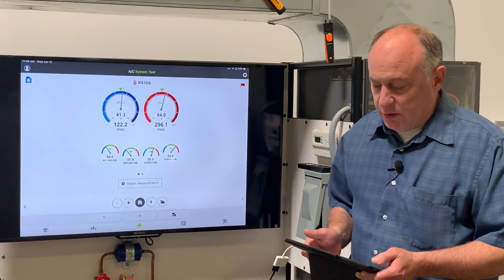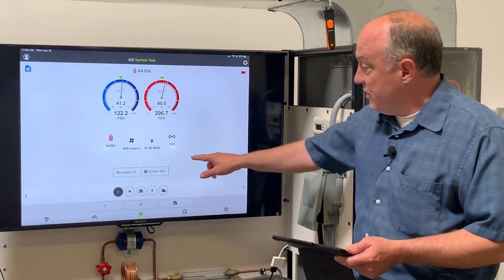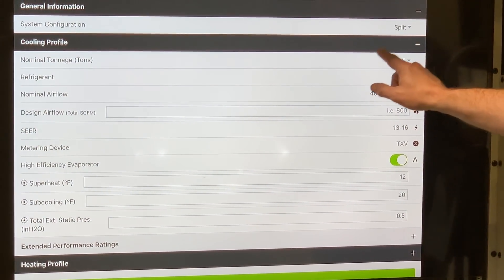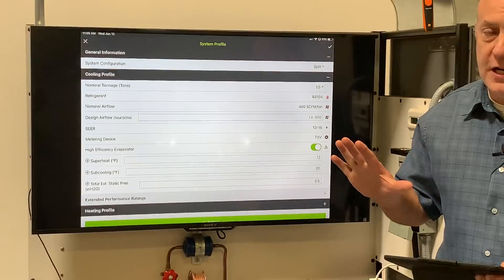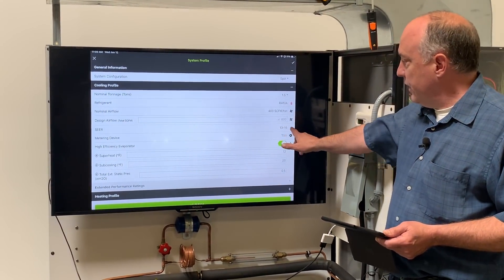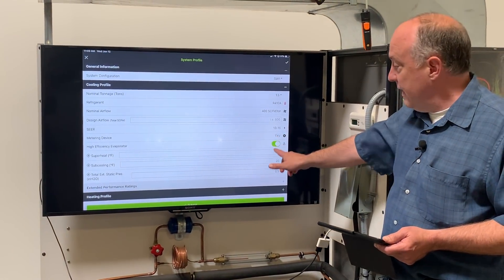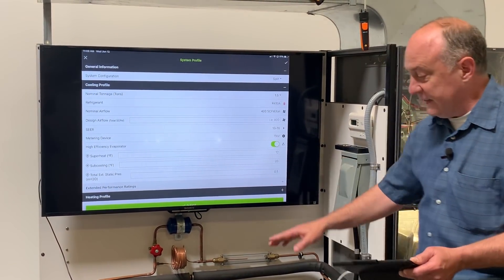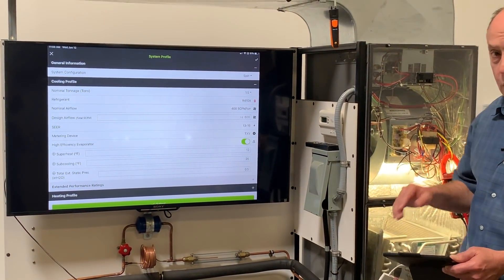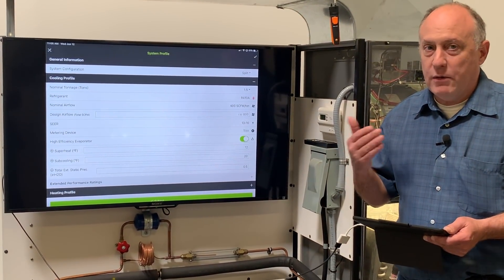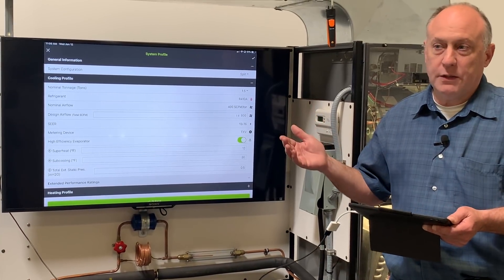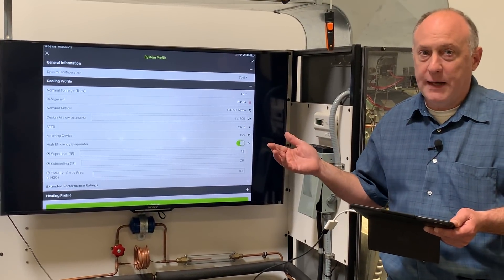One of the most important things to remember is that in the information section — system information — we have to make sure we're putting in the correct cooling profile. It's garbage in, garbage out. If you don't tell me what type of system you have, what the superheat targets are, what the SEER rating is, whether it's got a high efficiency evaporator — in this case a ton-and-a-half condenser with a two-ton evaporator coil — if you're not telling me those things, I really can't help you with a diagnostic. Just like going out and asking what's wrong with a unit without any information on it simply doesn't work.